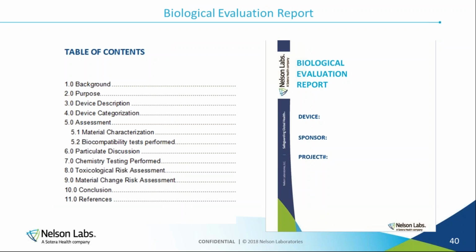So for a biological evaluation report, I just put in our table of contents. You could see some of the conversations that we would have. We give a background of the device, why we're doing all of this testing. Is it new? Did you change it? You're moving to a new market. It also gives you an opportunity to say, hey, it's already been on this market for this long. We have no adverse events reported. So again, another place to have that conversation where it's relevant to the safety of the device.